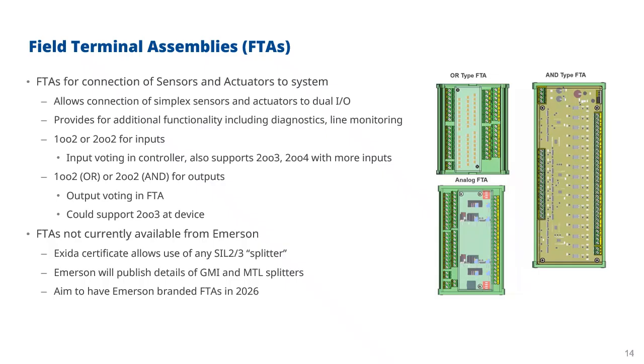Now, it is possible that some solutions will use duplex sensors and duplex actuators, in which case you might not need the field terminal assembly, but I would imagine at the SIL 2 level that's going to be quite rare. Normally you're only going to have a simplex sensor and actuator.